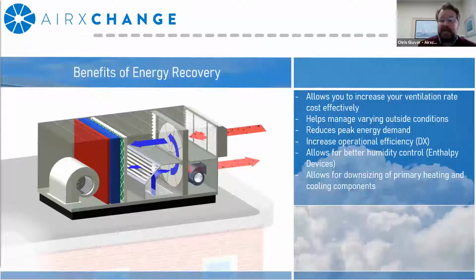And lastly, this is more for new construction, but it allows for downsizing the primary heating and cooling components. So as you shift the ventilation load from the primary heating element or cooling element over to the wheel, it means that you can downsize the subsequent system accordingly, because now the wheel or the plate is handling that load.